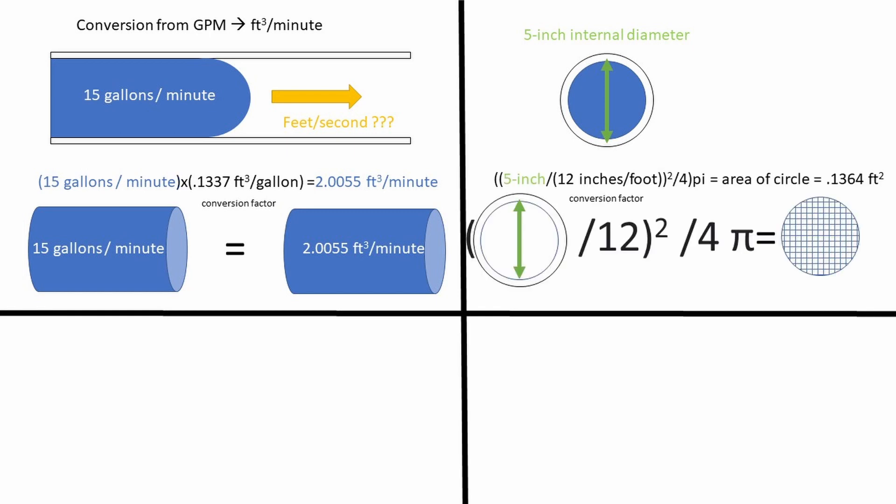Next, we must get our pipe internal diameter into a cross-sectional area that is in the units of square feet. We can divide our 5 inch diameter by 12 inches in a foot to get a diameter in feet. We can then use the area of a circle formula, which is the diameter squared divided by 4 times pi to get the internal cross-sectional area of the pipe.